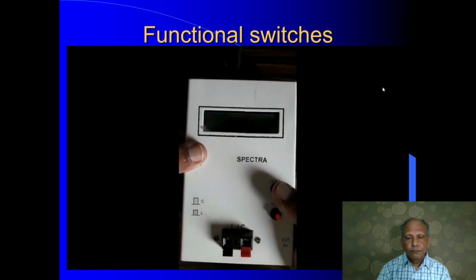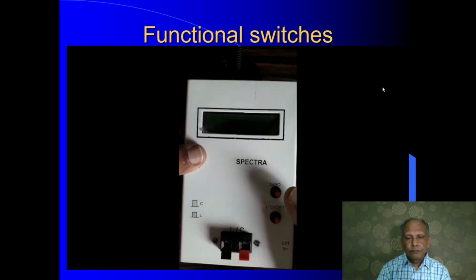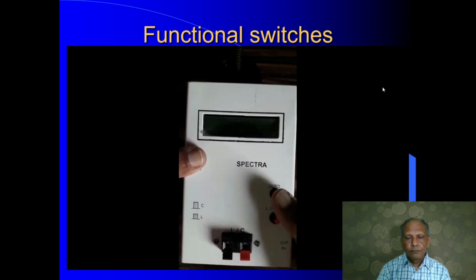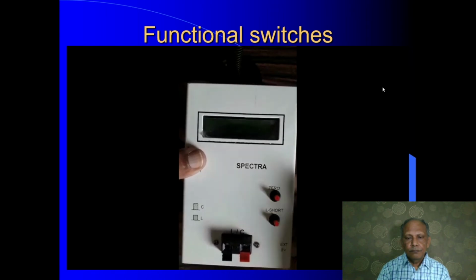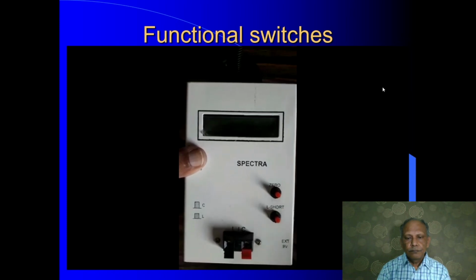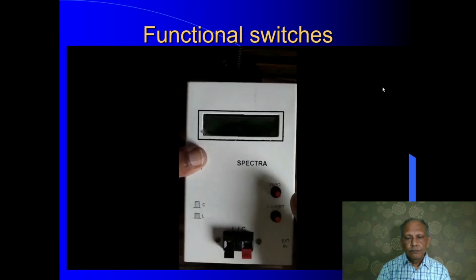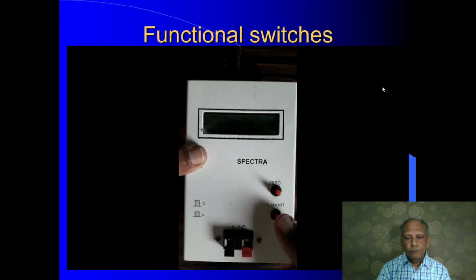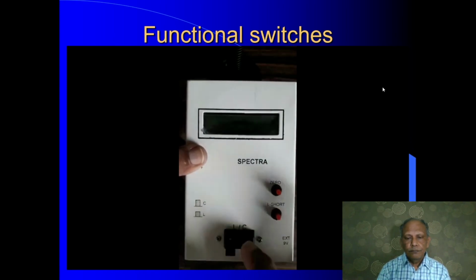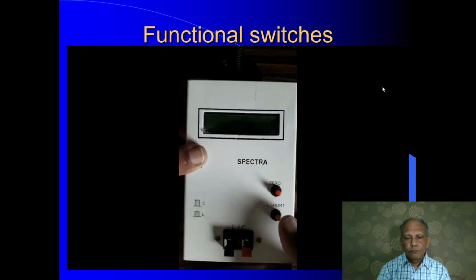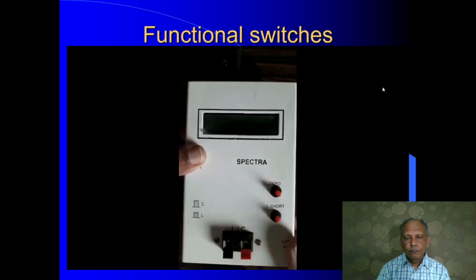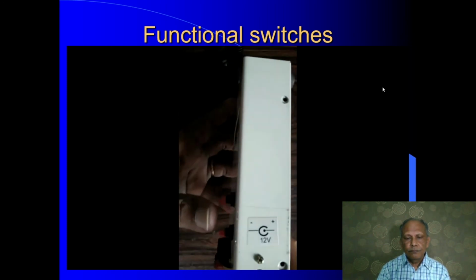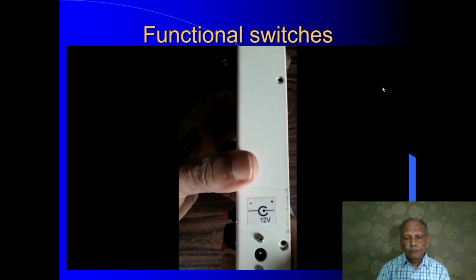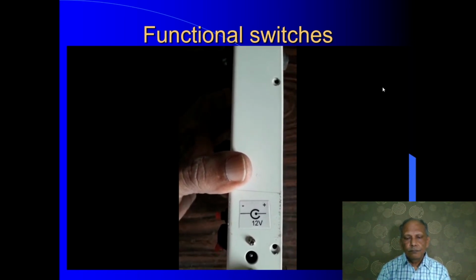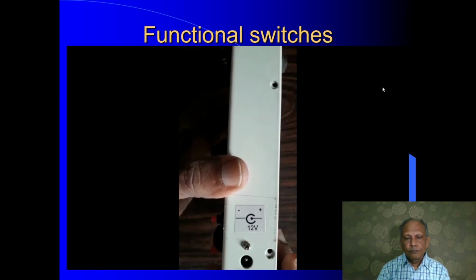Now here there is a zero switch. This is required for initial operation, making the reading zero. Once we switch on, it is always advisable to press the zero once, so that the internal calibration circuit will function and it will make it zero. Then there is an L short. This is equivalent to shorting these two terminals. It is useful only for inductance measurement. Then on the other side, we have only one socket to feed external 9 volts. This voltage can go up to a maximum of 12 volts.